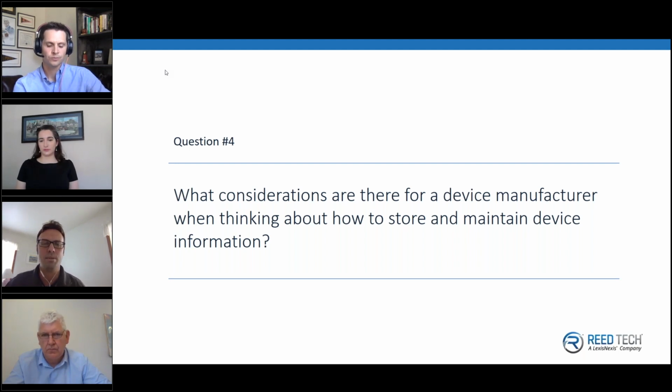From a U.S. example, something that we saw was the catalog number was not required to be included in the FDA GUDID submission. So there were instances where folks didn't include that in their submission to the FDA because it wouldn't fail validation. It's optional. But really, at times when the regulator is stating something as being optional, and I think the FDA perhaps even backtracked on that wording eventually and said we should have said if applicable or if available, they want that information.